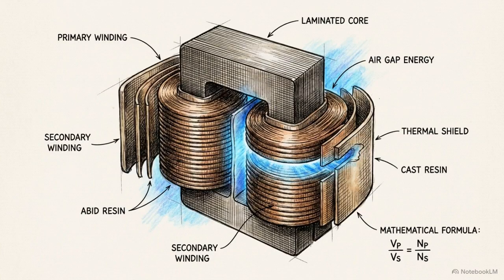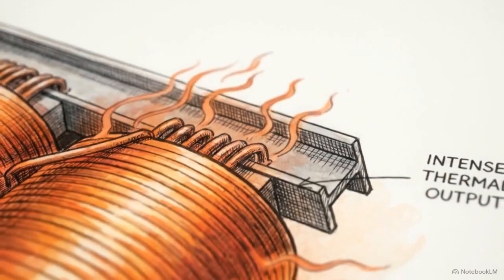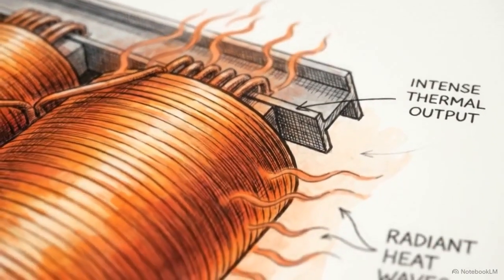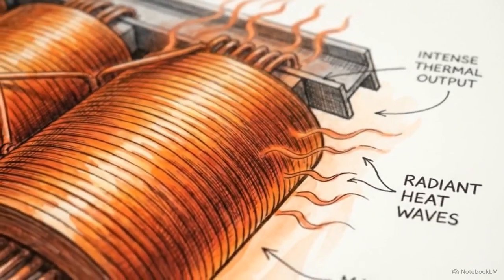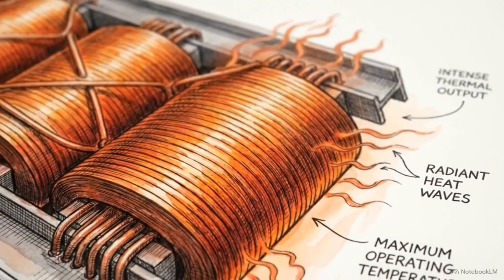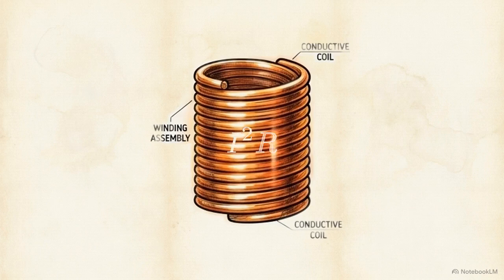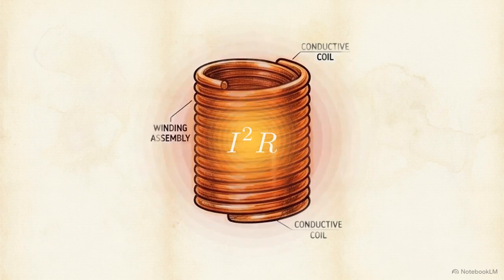Step 1 is managing thermal stress. A transformer operates by isolating circuits and stepping voltage up or down across its primary and secondary windings. As electrical current passes through these solid copper or aluminum coils, it encounters natural resistance, which constantly generates heat. We calculate this heat using the I²R formula, where current and resistance dictate an unavoidable escalating thermal buildup. Without a liquid cooling bath to dissipate this energy, the physical paper and resin insulation wrapping the windings becomes the system's most vulnerable failure point.